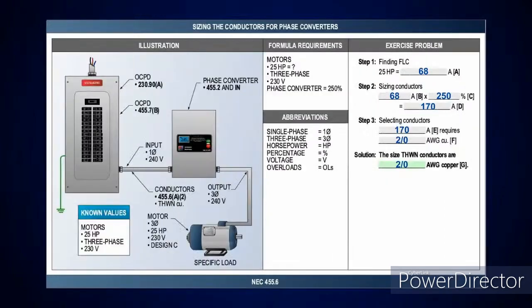All right. Now, here you got a phase converter. And when you go over and look at sizing the conductor in 455.6A2, it's going to tell you that you've got a fixed specific load here, and it's going to tell you to take it at 250%. But it's also going to tell you that you have to protect the conductor, or you have to protect the amperage rating that's there. So that means I'm not going to go down. I'm going to actually size those conductors up at that point.